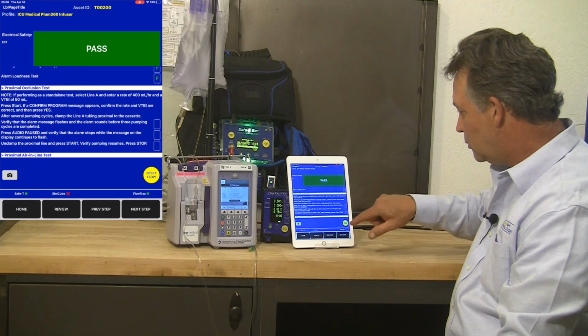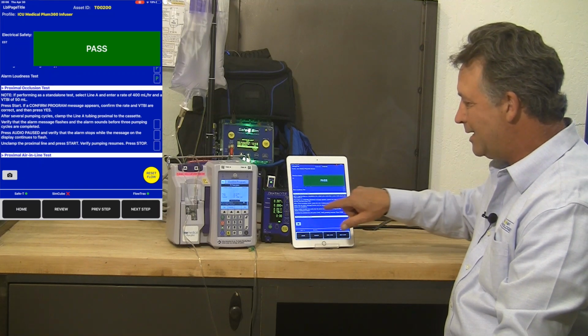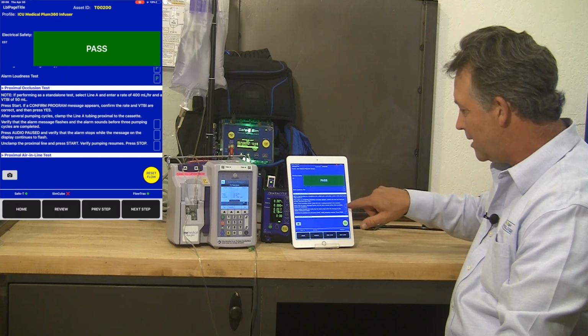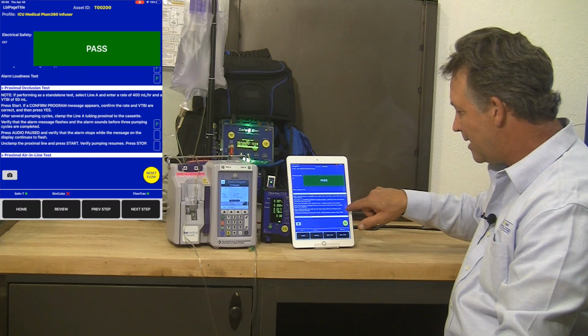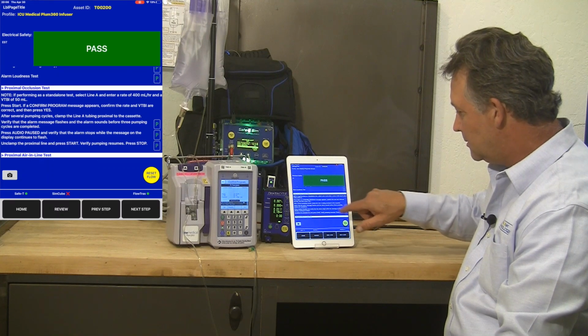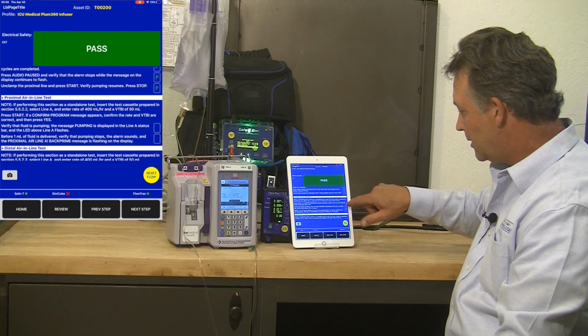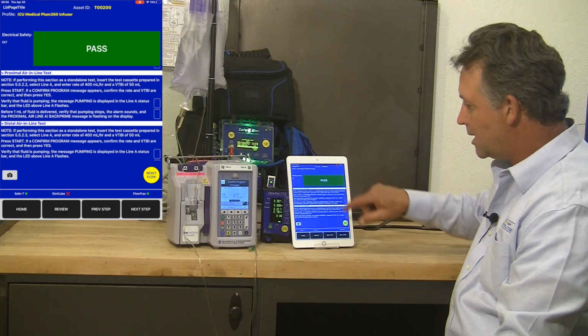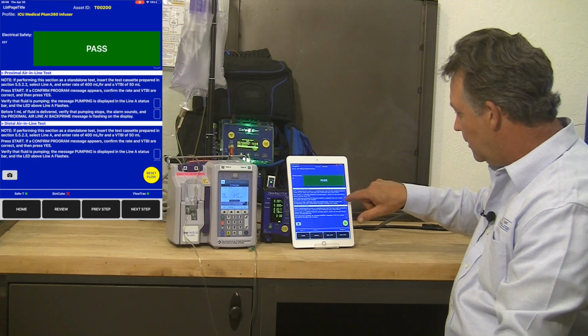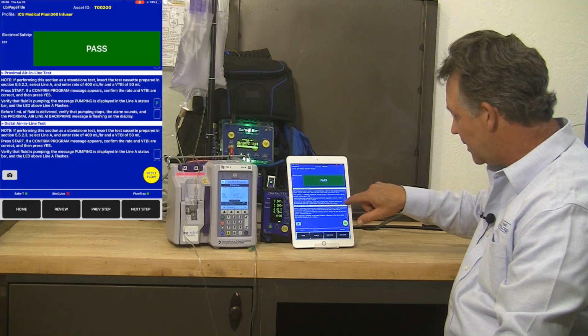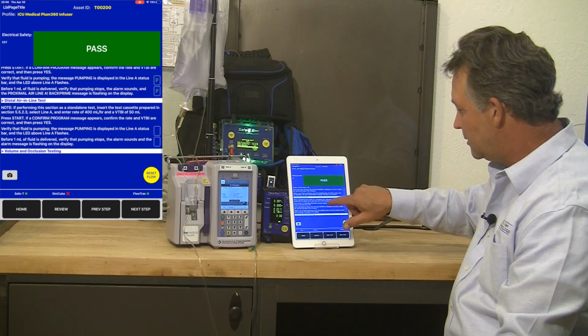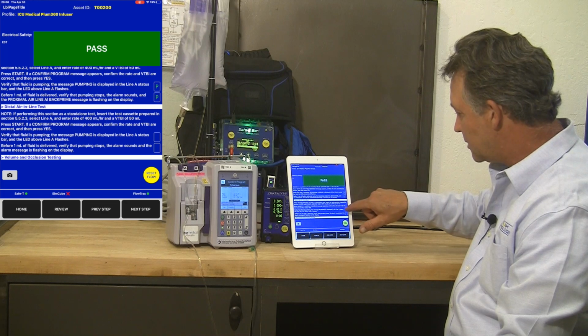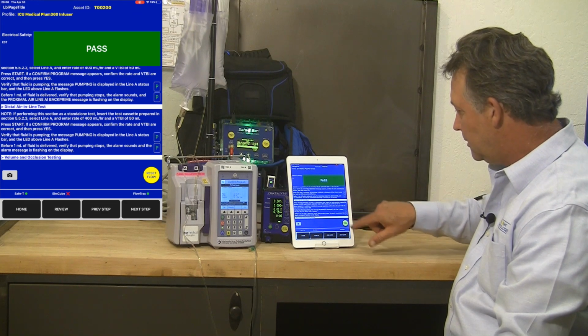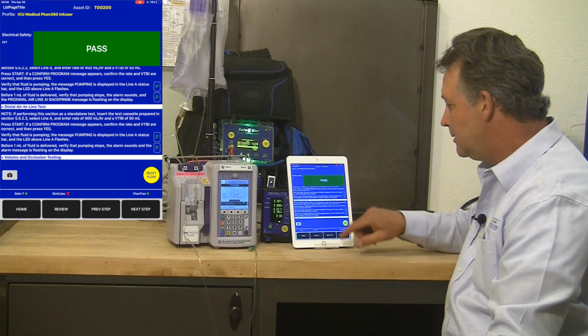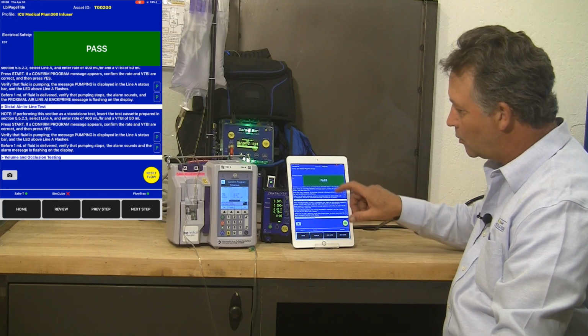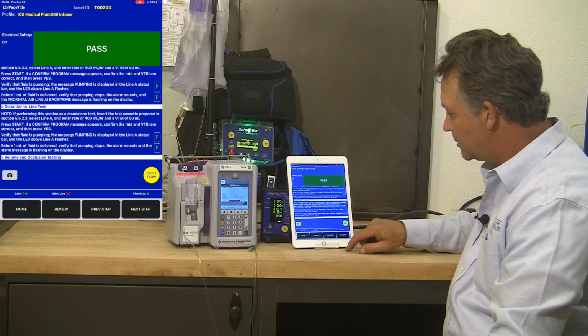I'm at the proximal occlusion test. The actual text guiding you through that particular test is on the iPhone or iPad screen, just like it would be on a hard copy checklist. I can walk through that test, select pass or fail. Proximal air-in-line test, same thing. We're displaying the exact verbiage from the service manual from the manufacturer and allowing the user to run each test individually and select pass-fail. The distal air-in-line test comes up next. I can select pass or fail, and then I reach the volume and occlusion testing, which we will show you next, where we're actually controlling and capturing results from the IV pump analyzer.